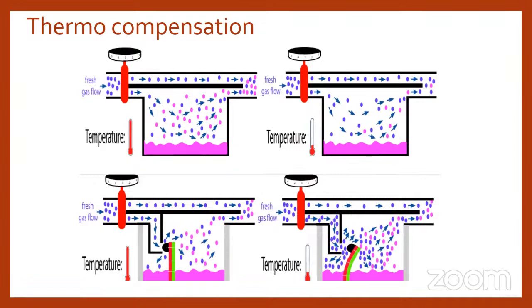As you can see, when the temperature is high, in the bottom left one, the control rod will be straight, blocking the amount of fresh gas that enters the vaporizer. So it limits the fresh gas flow through the vaporizer. A limited amount of fresh gas will enter the vaporizer, a limited amount of vapor will mix with the fresh gas, and it will be sent out through the outlet to the patient. When the temperature is low, when the vaporizer gets cooled, the green side of the temperature control rod will contract, which exposes the blockage between the vaporizing chamber and the fresh gas flow chamber. So the fresh gas entering the vaporizing chamber will be more.